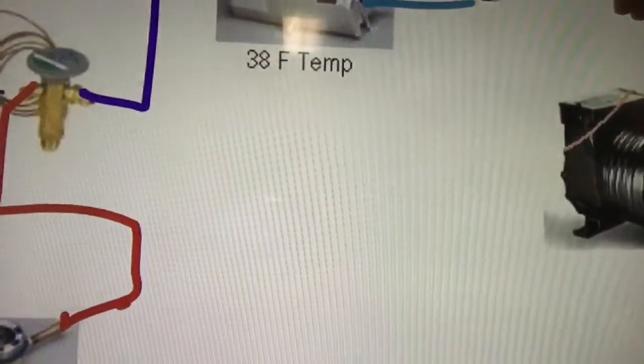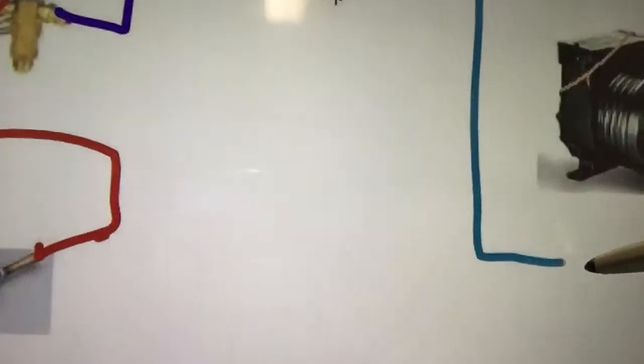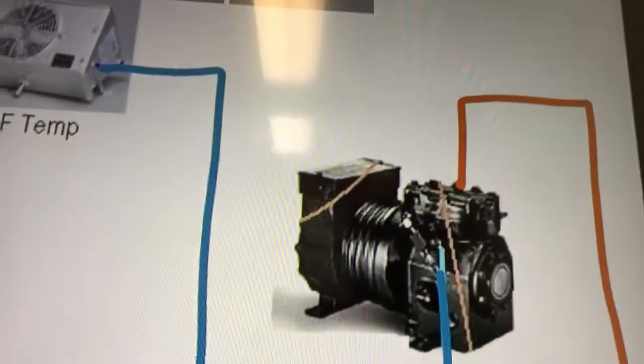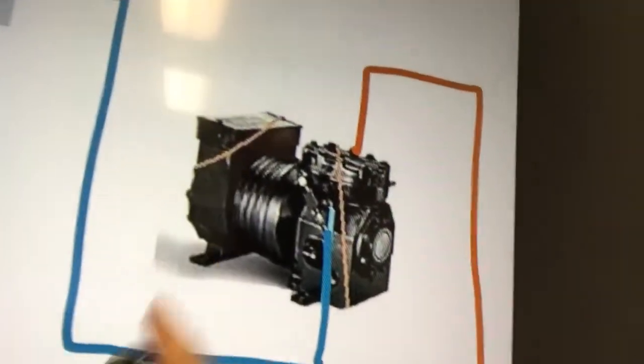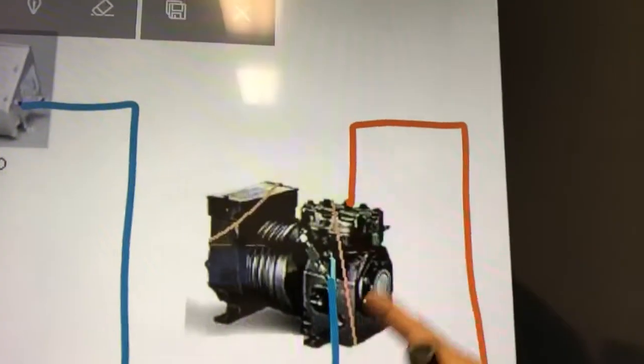From the evaporator, we change the color to light blue. Now the refrigerant coming out of the evaporator and going back to the compressor is 100% vapor, medium temperature — only vapor. This covers the different stages of the refrigerant from the compressor through the condenser, receiver, filter dryer, sight glass, TXV, and evaporator.